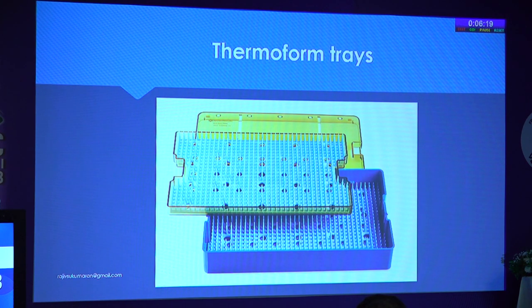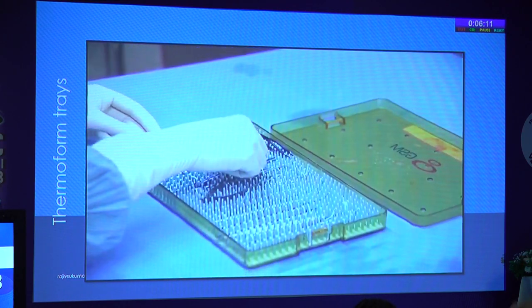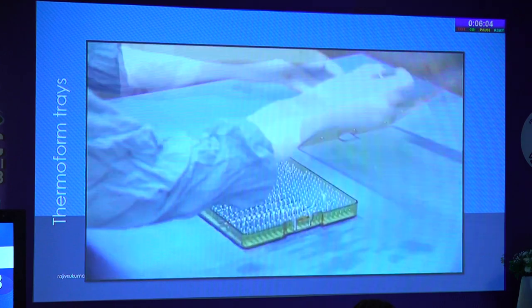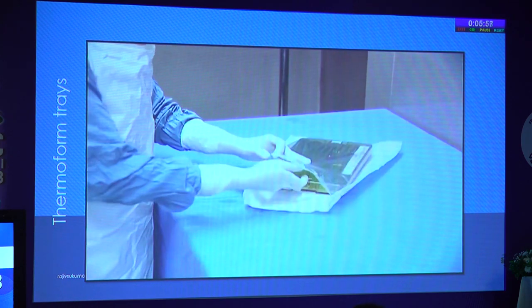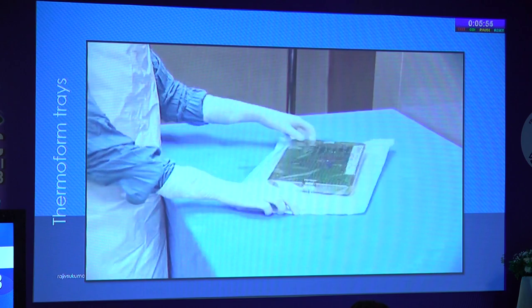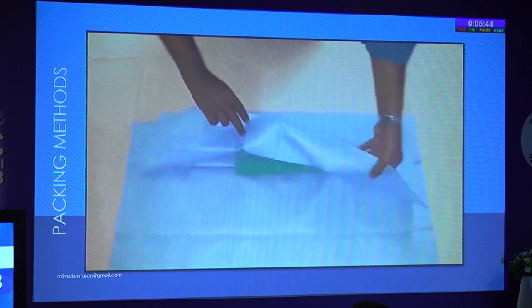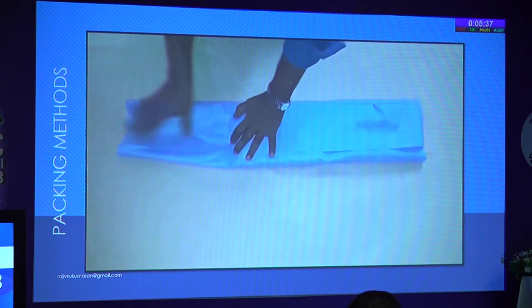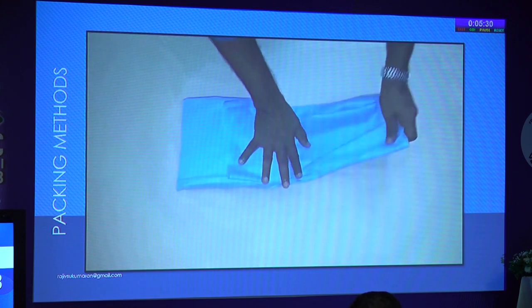The best way to pack instruments: use a perforated tray or thermoform tray, pack carefully without damaging instruments, and before closing, put an autoclave indicator inside — preferably Class 5 or Class 6. Then put it in a pouch and seal it. This is the easiest and best way in ophthalmic practice. The type of wrapping is also very important. The parcel method involves folding in a square pattern with a leading edge so that you can hold it when opening without contaminating the inner surface.